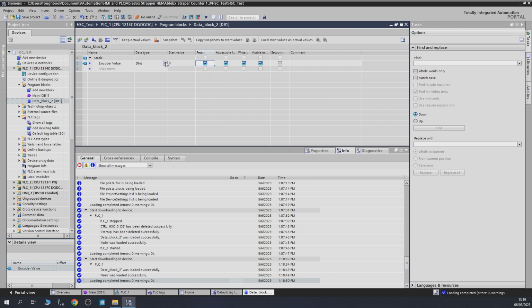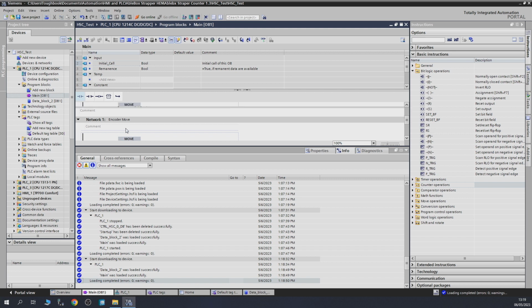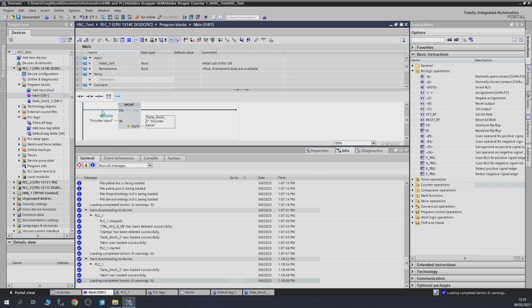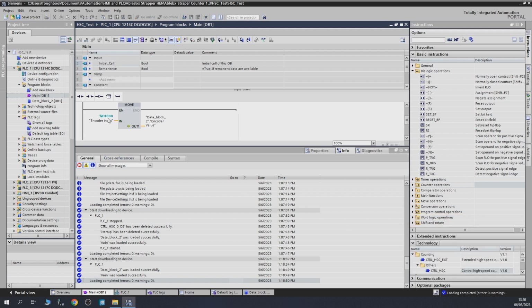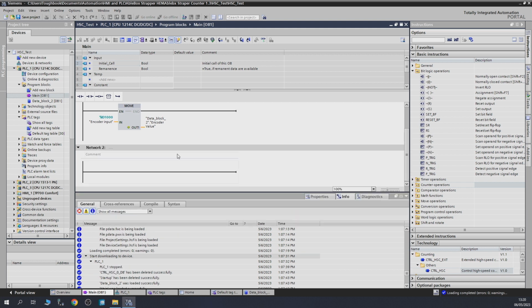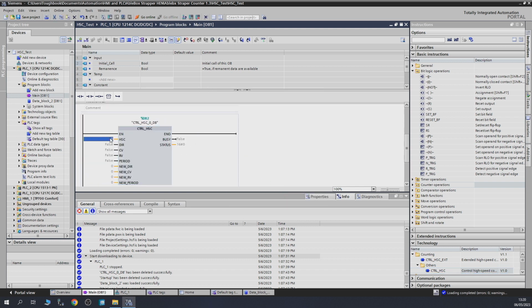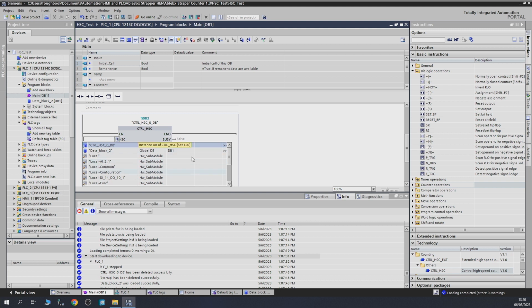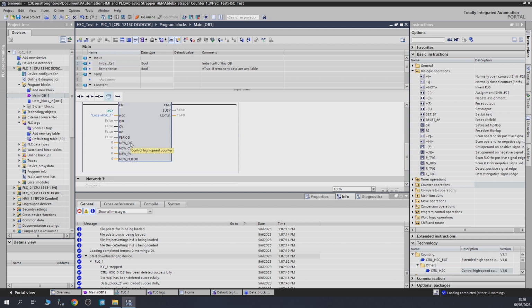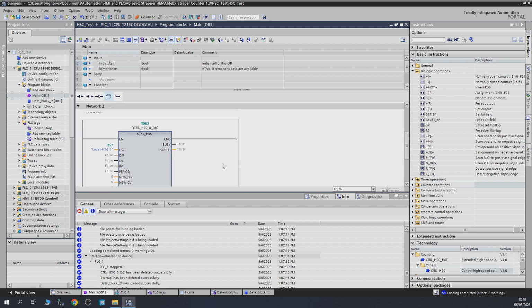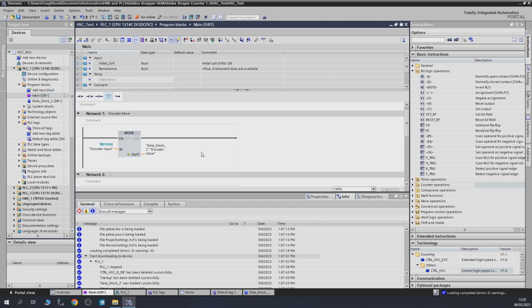So we somehow need to update ID 1000, and to do that, we can have a bit of help from the controller for high-speed counters. So let's have a look at what we can do for that. First things first, let's take this counter in here because we are going to need that one. It's going to create our data block for that. Let's say this controller is going to be working for HSC1. Several things can be done in here, and one of them is you can change ID 1000's value. But we need to do that on startup somehow.